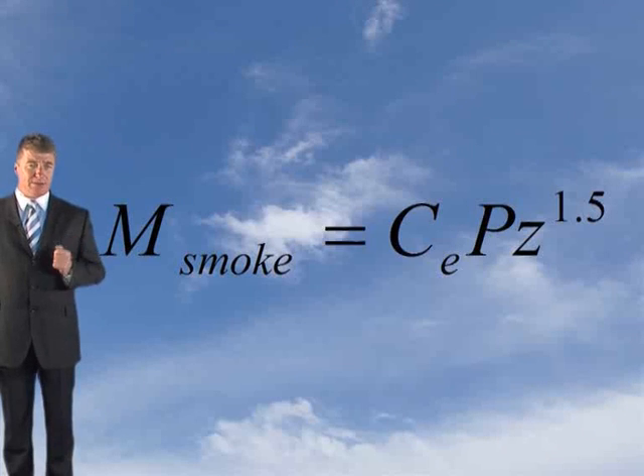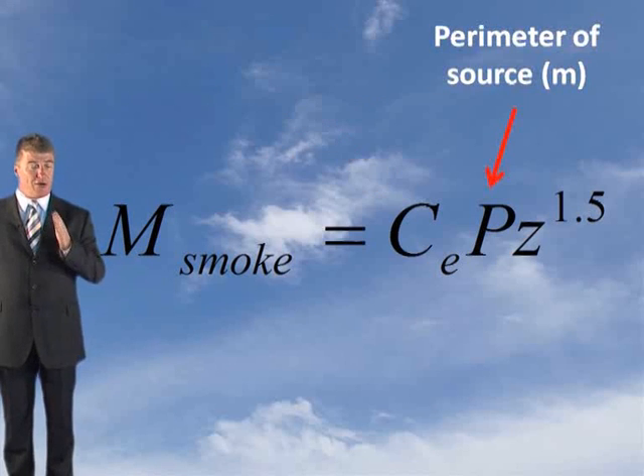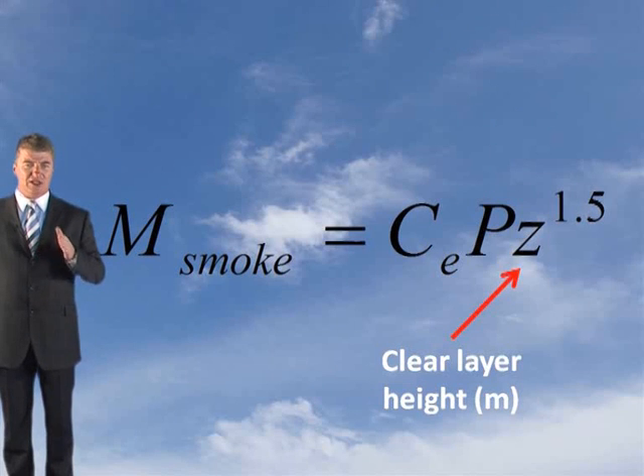The model for the axisymmetric plume is: M_smoke equals CE (the coefficient of entrainment) times P (the perimeter of the source) times Z to the power of 1.5, where Z is the clear layer height. To apply this model you need to determine which coefficient to use. There are three options: 0.19, 0.21, or 0.34.